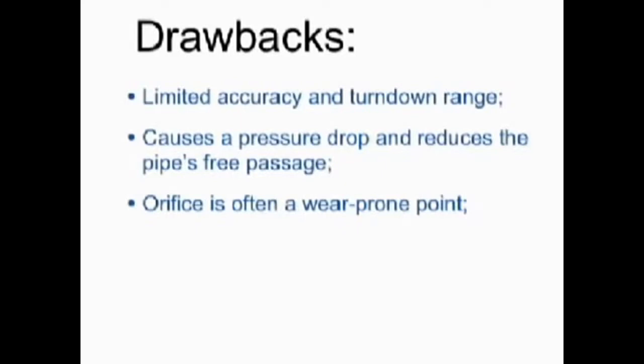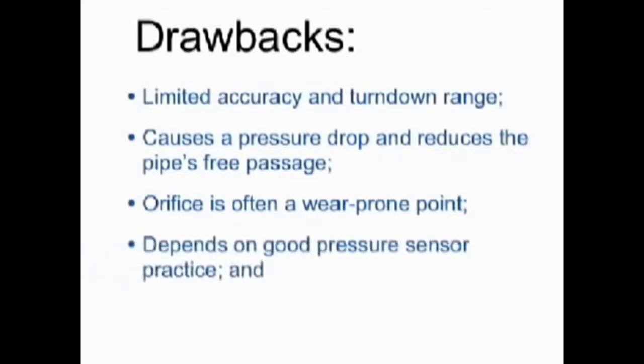On the other hand, if it becomes partly obstructed with debris, the measurement will read higher. The same application and installation guidelines for good pressure sensor practice apply here. Anything that interferes with the pressure readings, such as clogged impulse lines, will interfere with the true flow calculation.